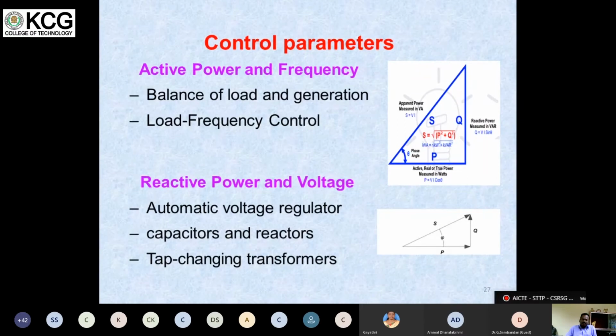And capacitors and reactors. Capacitors are called reactive power generators. Reactors are called absorbers of reactive power. When the voltage is more, we switch on the reactors to absorb the reactive power so that voltage can be maintained. Normally, these reactors are provided at the receiving end of the 400 kV and 750 kV lines, so that switching surge does not happen. And of course, we have the tap changing transformer also. Transformer tap change will increase or decrease the voltage in the system, and it also absorbs reactive power or gives reactive power to the grid.